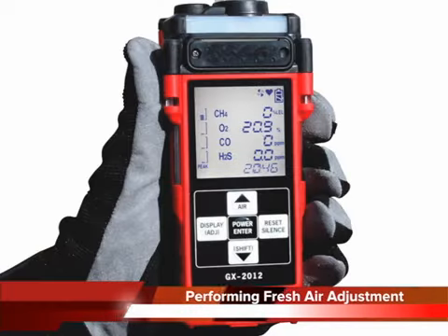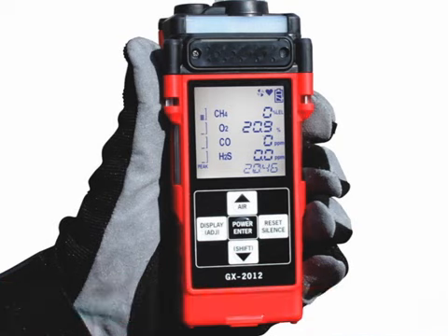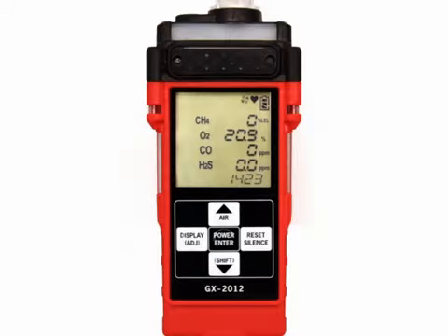Before using the GX-2012, you should perform a fresh air adjustment. Make sure you are in a fresh air environment which is free of toxic or combustible gases and is of normal oxygen content. Normal oxygen content is 20.9%. With the unit on and the display showing the normal operation screen, press and hold the air button.